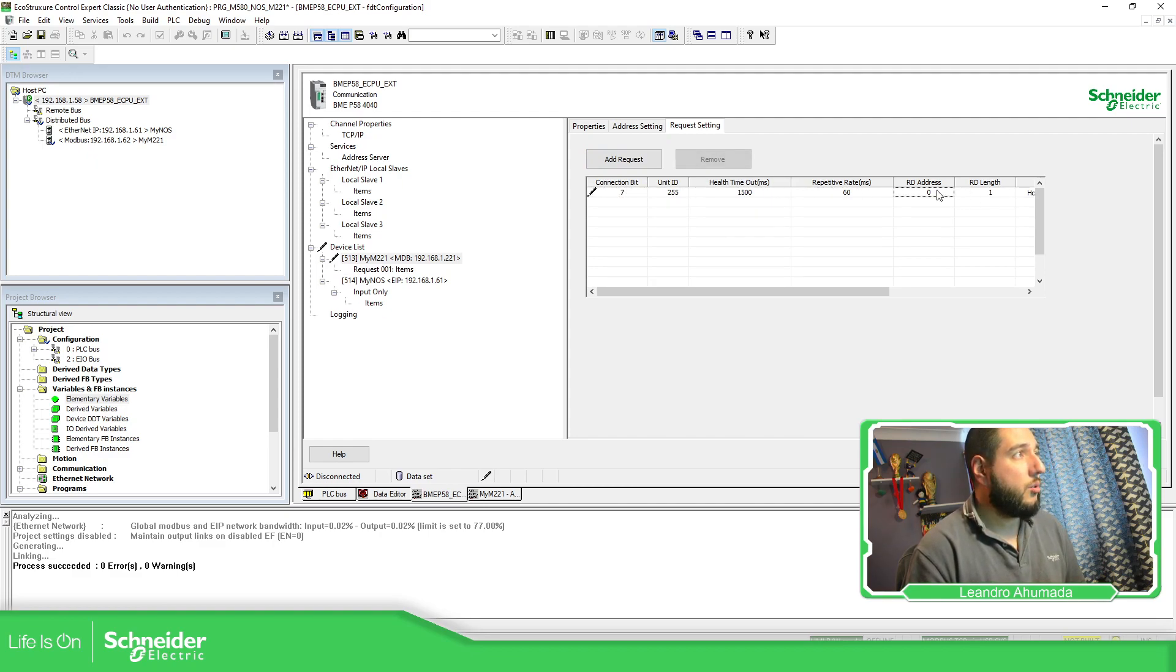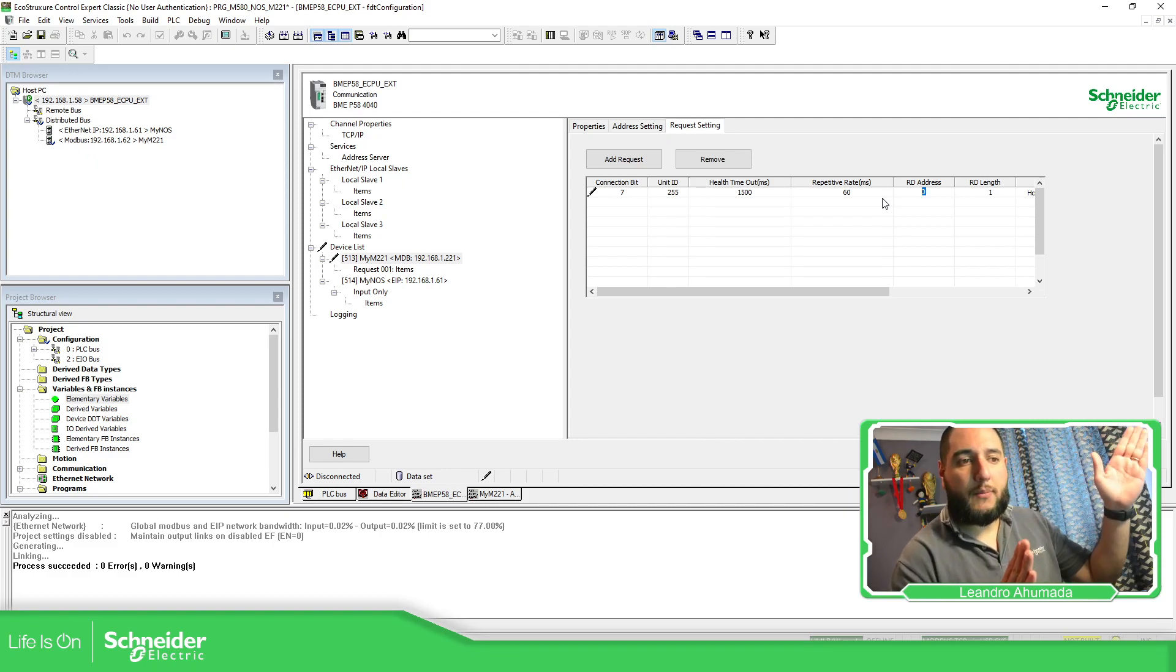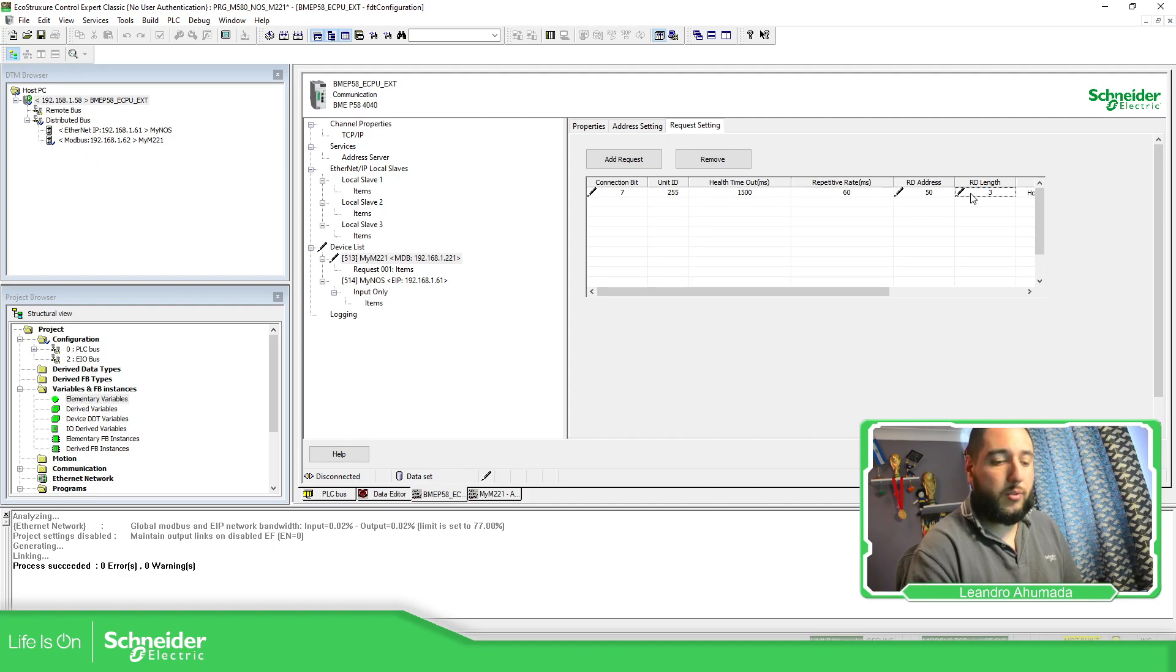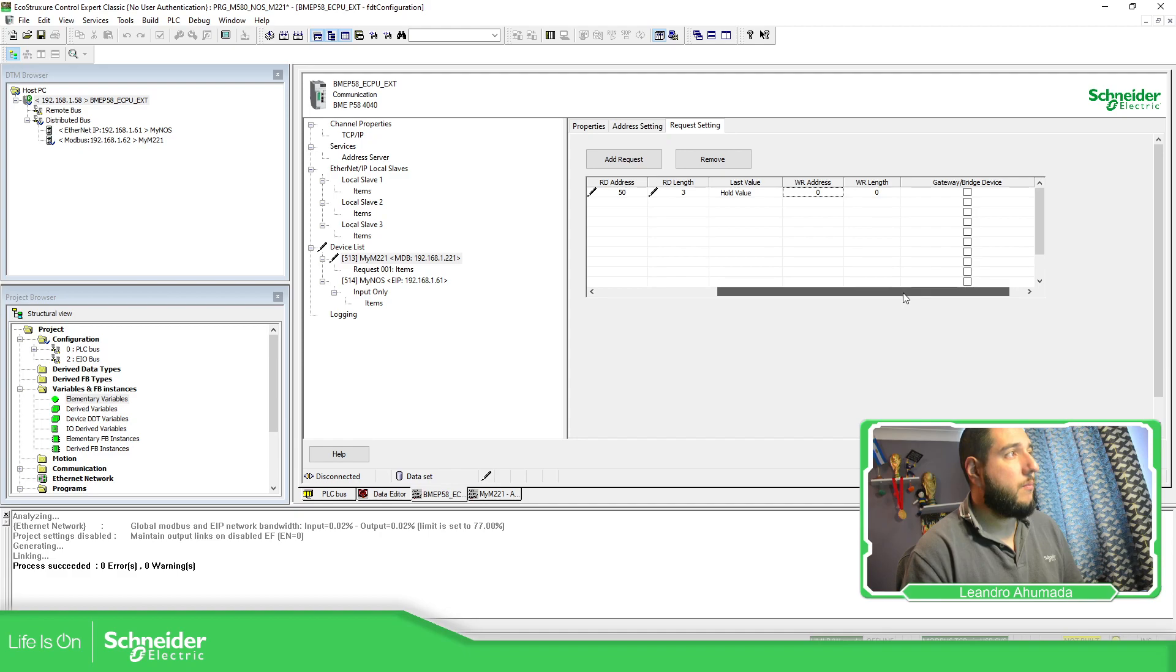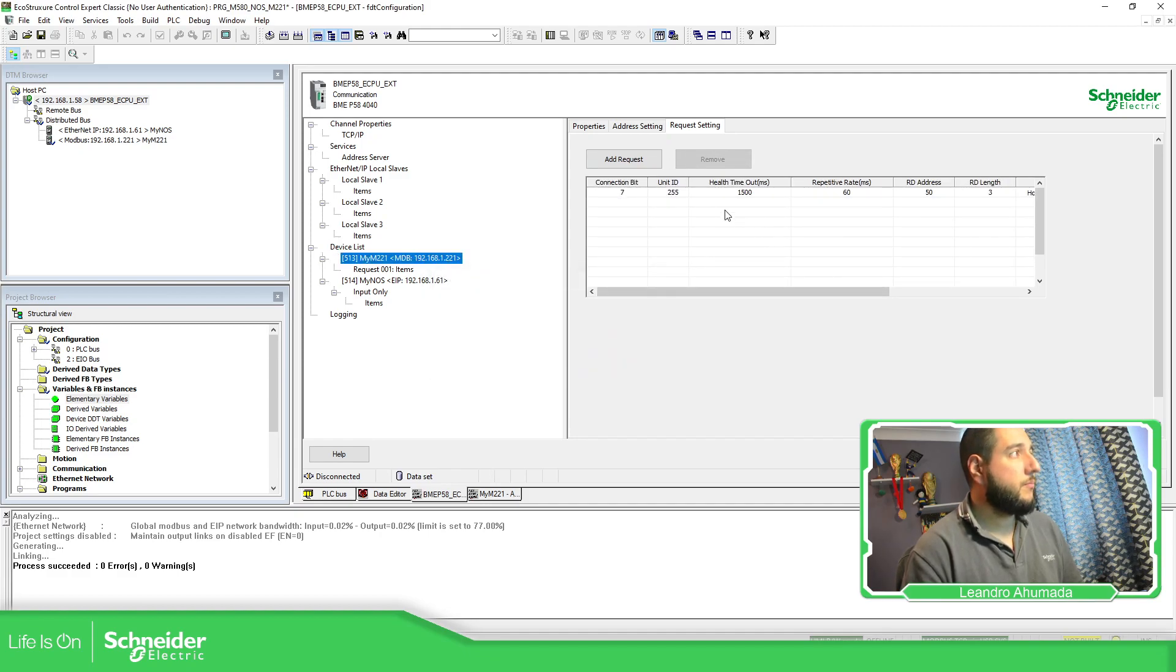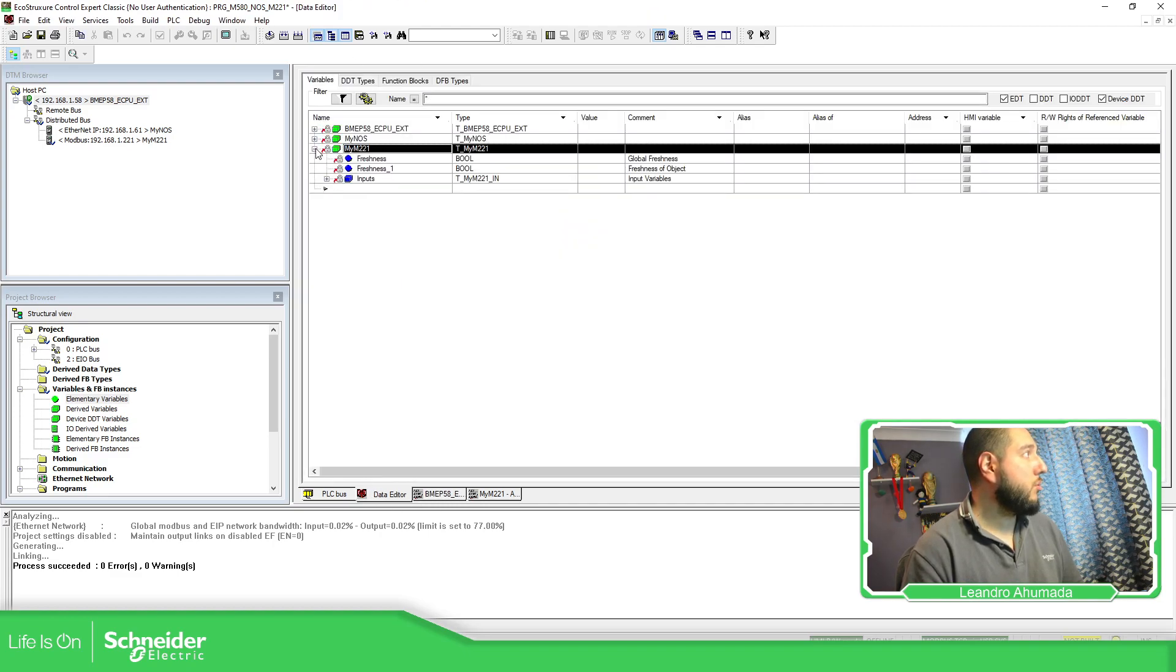And here on the request is where do you need to define the information to where to read the data. So add. Here I'm going to use the read. So I'm going to read from the position MW50 and I'm going to read three words on the device. You can also put the write, but I'm going to generate a different connection. So apply.